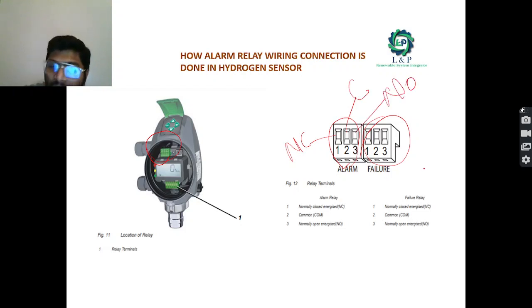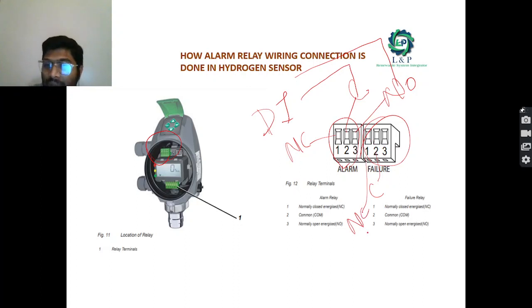The same applies if you want to do the alarm relay wiring. You want to connect your signal cable, DI cable with this, you can connect your common here and your NO. Okay, and the same way, if you want to do the failure relay wirings also, you can do it. This is the common point. Okay, and if you want to do the NC connection, you can do it like this. You can connect the NC cable here. So this is how basically the DI connection for alarm and failure relay is done inside the hydrogen sensor.